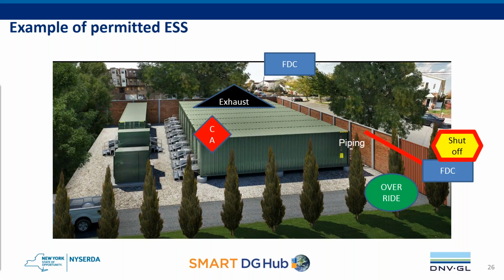They also have an exhaust in each one of these containers. If the incident commander on the scene felt that he needed to exhaust the container for a potential flammable gas that may accumulate as a result of a thermal runaway event, he can override the exhaust system and start to exhaust any flammable gases that may be contained on the inside. Along with that, there would be a shutoff on each side, there for the fire department to shut off if there was an emergency and they needed to shut these things down.